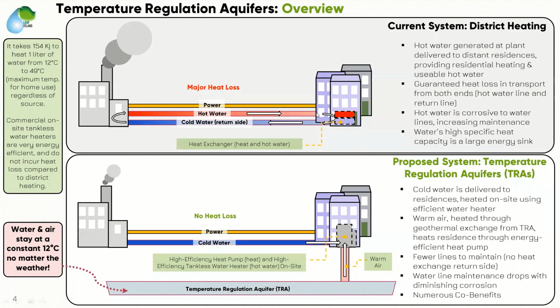Each house has a heat exchanger in the basement that takes the incoming water and transfers heat from one portion to another to make it hotter, since everyone wants hot water in their showers and pipes—it's essentially a steam heating system, like a radiator. The heat exchanger splits the hot water from the plant into two streams: one hot stream goes to your shower and pipes, and the colder stream returns to the plant on the cold water side.